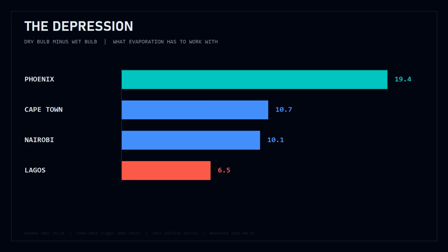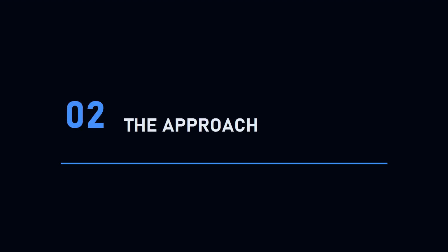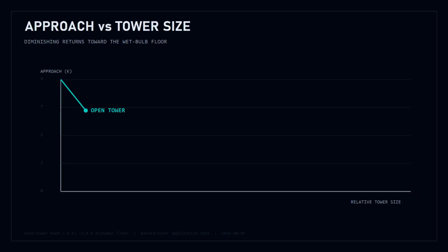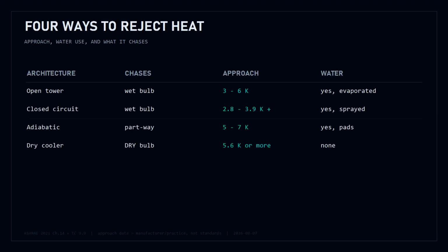In practice, you never reach the floor. You stop short of it. And the distance you stop short is the approach. An open cooling tower, 3 to 6 Kelvin above wet bulb. Below about 2.8, the economics collapse. No manufacturer will guarantee it. A closed circuit cooler, 2.8 to 3.9 or greater. That is a floor with no ceiling attached.